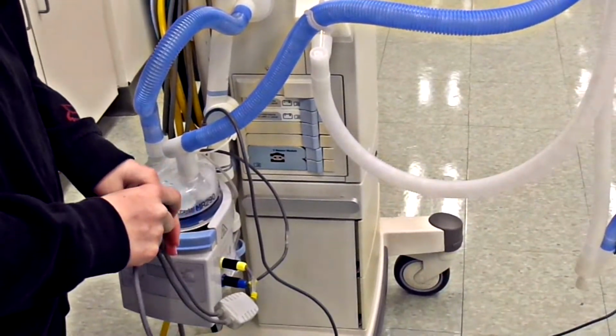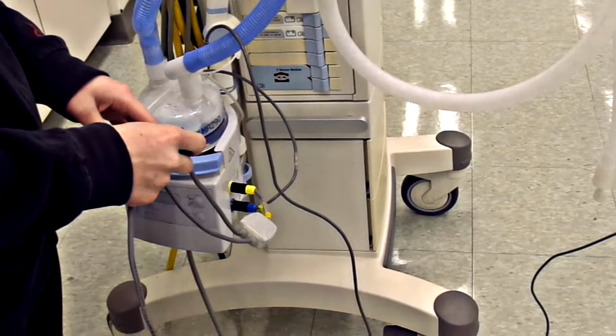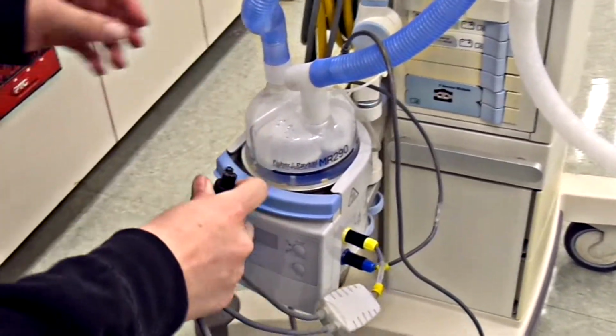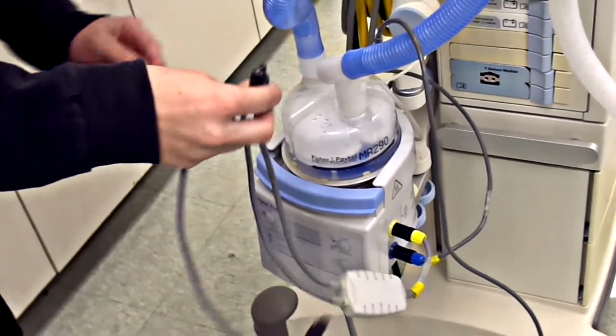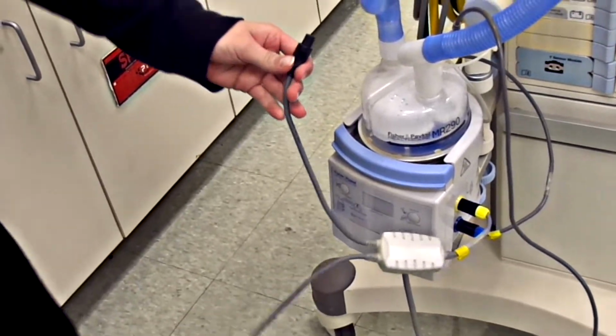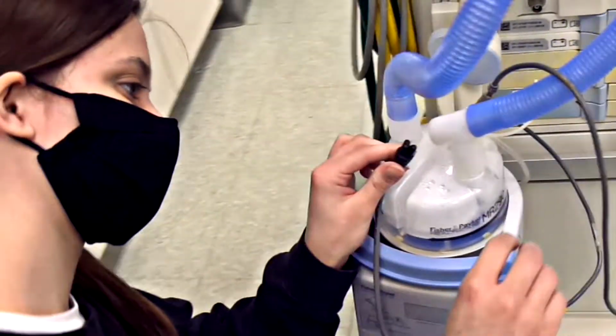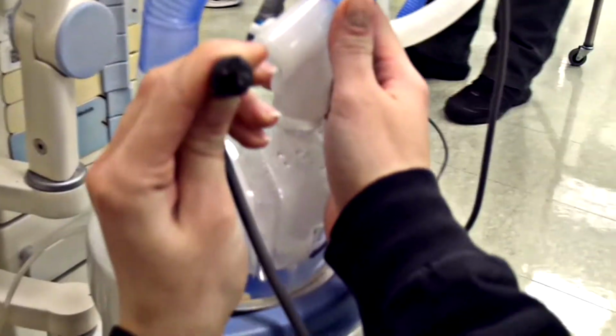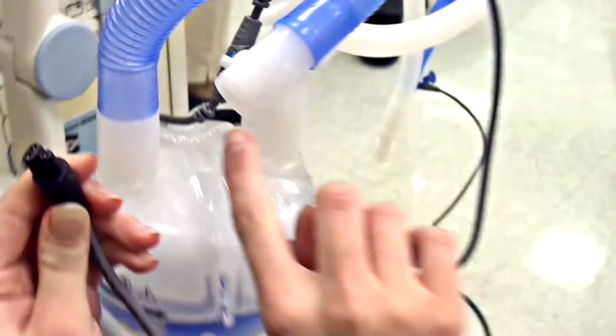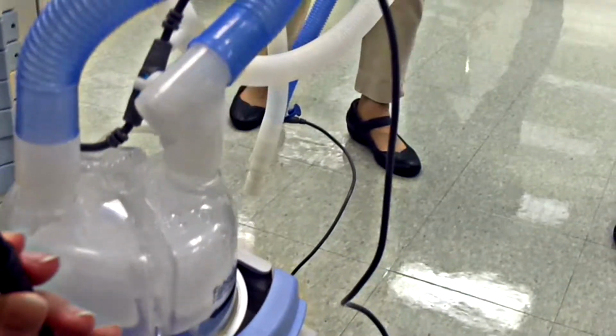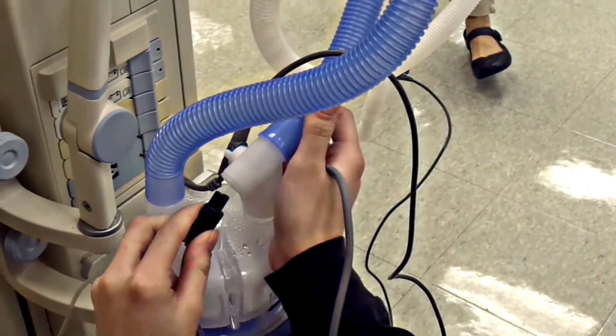Number 2, the top connection, yellow, is the attachment for the heater cable. You will notice the cable has 2 plugs. Attach one plug into the inspiratory side, the other plug connects at the expiratory side at the end of the tubing. These wires heat up the circuit. The purpose is to prevent cooling of the gas. A gas that cools as it travels through the circuit can produce condensation in water.